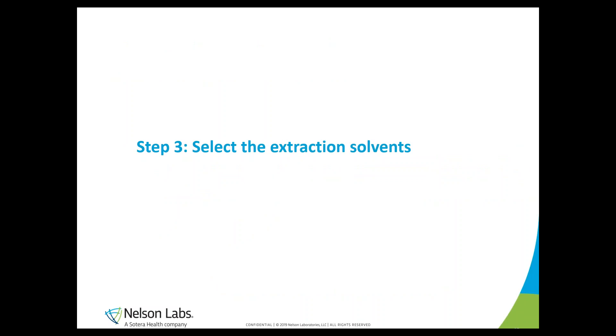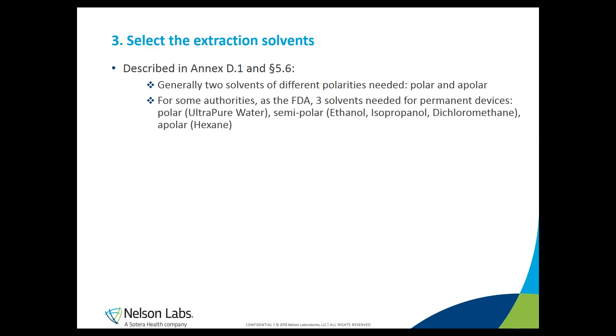The extraction solvents will also be recommended in this final draft. In the previous version, there was a lot of referral to part 12 for sample preparation, but this will be much less important in part 18. Extraction solvents are described in Annex D.1 and paragraph 5.6. Generally, two solvents of different polarities should be used — a polar and an apolar one — in line with part 12. For some authorities such as the FDA, three solvents will be needed for permanent devices: a polar, a semi-polar, and an apolar one.